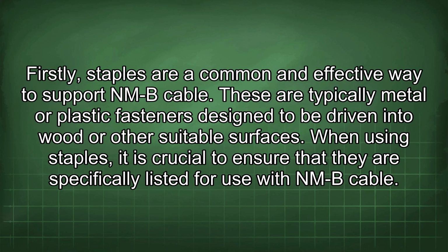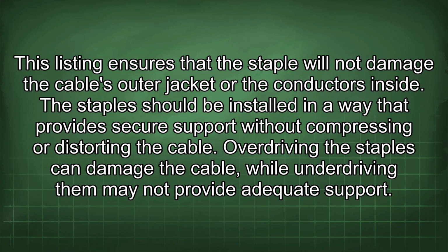Firstly, staples are a common and effective way to support NMB cable. These are typically metal or plastic fasteners designed to be driven into wood or other suitable surfaces. When using staples, it is crucial to ensure that they are specifically listed for use with NMB cable. This listing ensures that the staple will not damage the cable's outer jacket or the conductors inside. The staple should be installed in a way that provides secure support without compressing or distorting the cable. Overdriving the staples can damage the cable, while underdriving them may not provide adequate support.